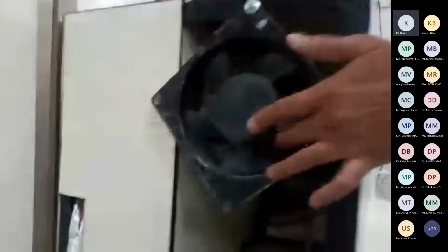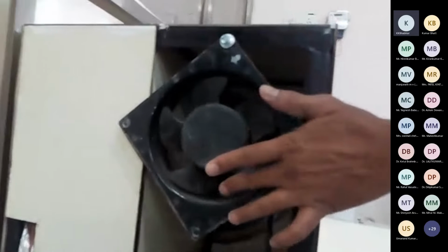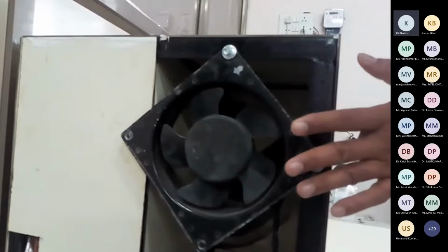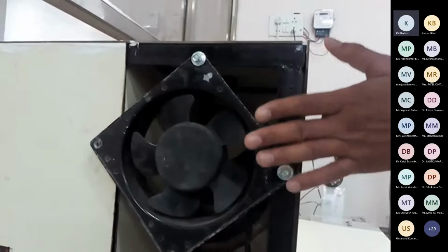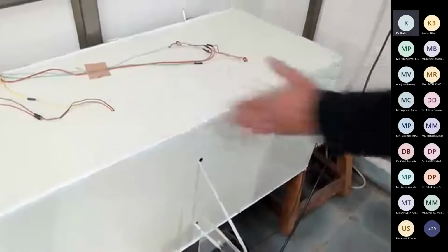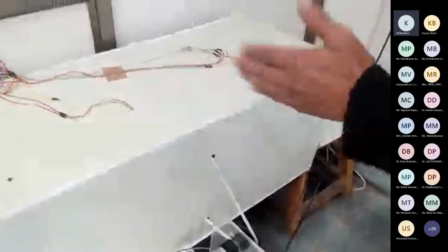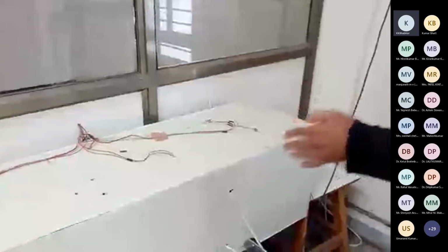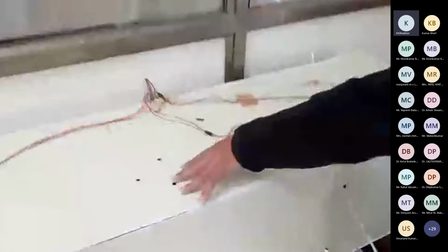Now, this is the exhaust fan, and this is the suction fan which supplies the atmospheric or ambient air to the regeneration section. Over here we are putting the enthalpy wheel, and over here we are putting the desiccant wheel. This is separately divided into equal parts, and then we are creating one section in which one heating element is provided in the regeneration unit.